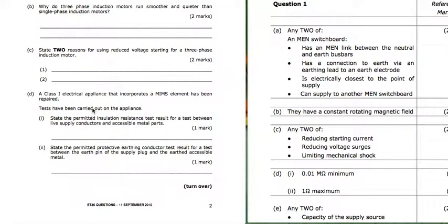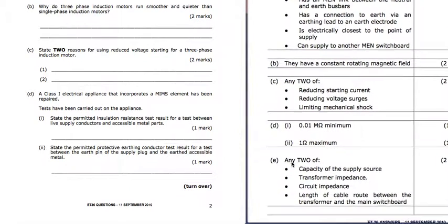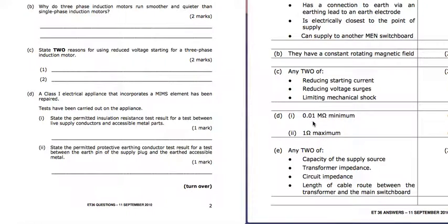D. Class 1 electrical appliance that incorporates a MIMS element. Now as soon as you see this MIMS, alarm bells should start ringing because they're a special thing when it comes to insulation resistance. So they're asking for the permitted insulation resistance test result. Now usually we talk about 1 mega ohms for insulation resistance, but if there's MIMS in there, it's 0.01 mega ohms or 10 kilo ohms. So we're allowed a lower insulation resistance.